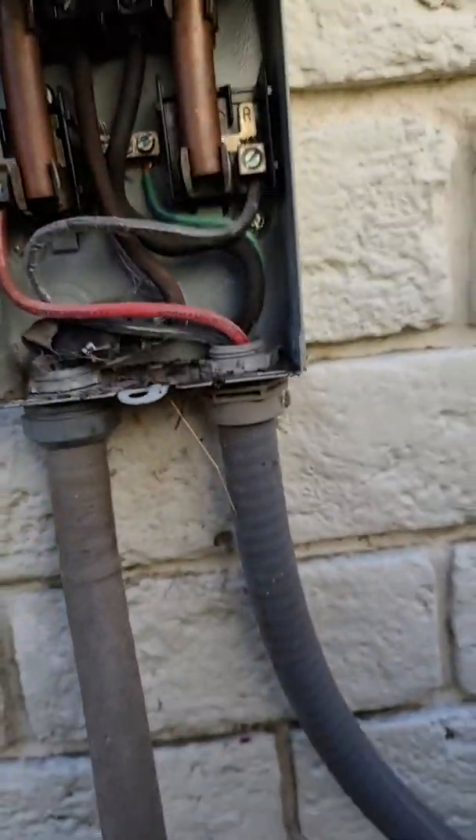So we have to check the breaker panel and make sure that there's a breaker that's rated for this system installed there. If not, then what we have here is an electrical issue and a fire hazard, because if there's ever an electrical short and these copper pipes are installed, they're not going to blow when a certain amount of amperage is put through the system.